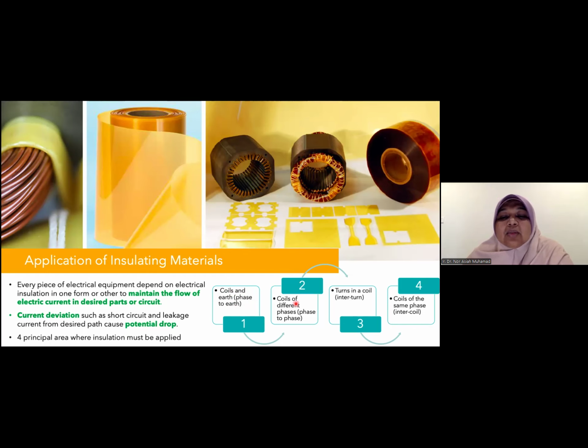Then between the coil and the coil, which is where we have phase A, phase red and phase yellow. In a power system we have a single phase system or a three phase system that run together. So we don't want the phases to be shorted, so they must be insulated. Between turns in a machine, in one phase there are a lot of turns. So we also don't want a short circuit between turn to turn. Then we need to insulate the turns, and also coils from the same phase, to avoid being shorted between them.